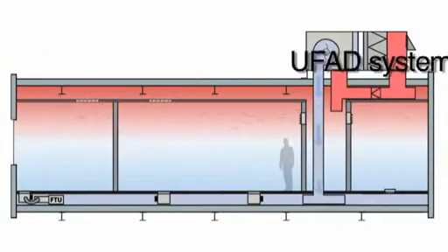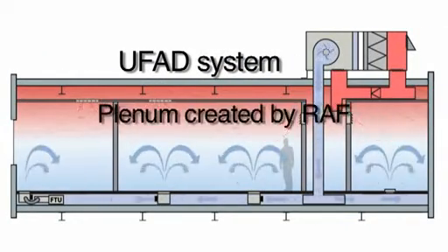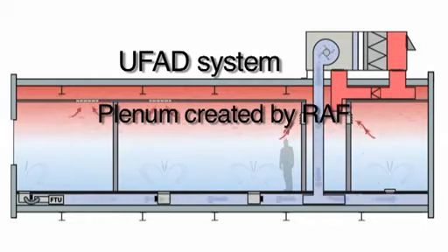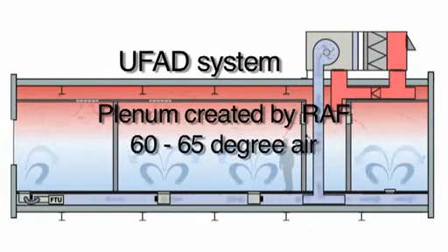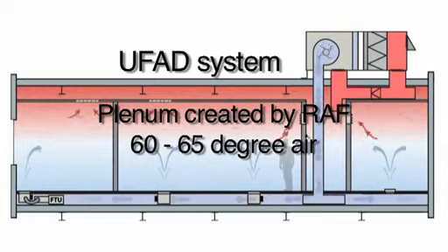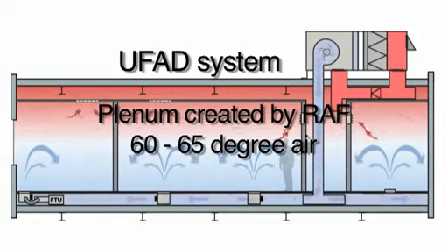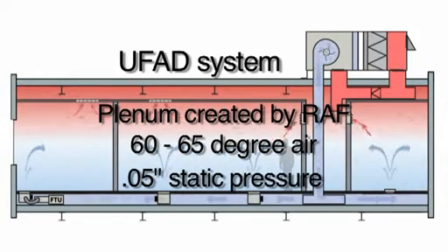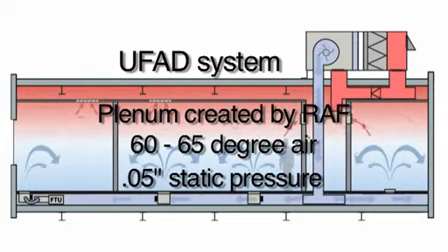Underfloor air distribution uses a space beneath the raised access floor — usually 14 to 18 inches — as a pressurized plenum, which contains 60 to 65-degree air. This plenum essentially acts as a duct throughout the entire floor plate. The plenum is pressurized to approximately 0.05 inches of static pressure and air is delivered at lower velocities through floor-mounted diffusers.